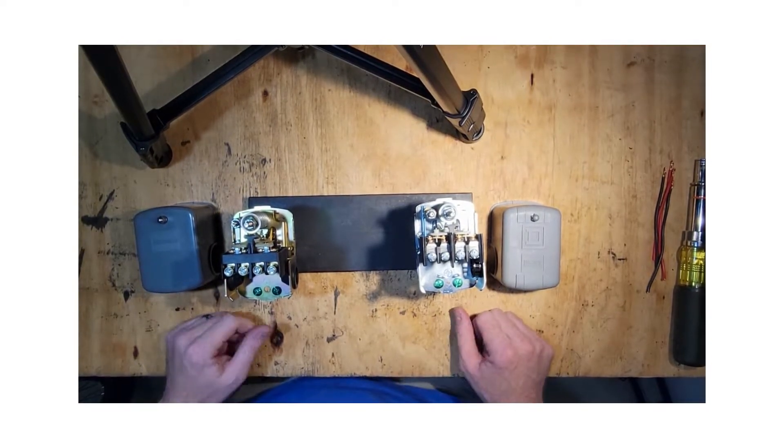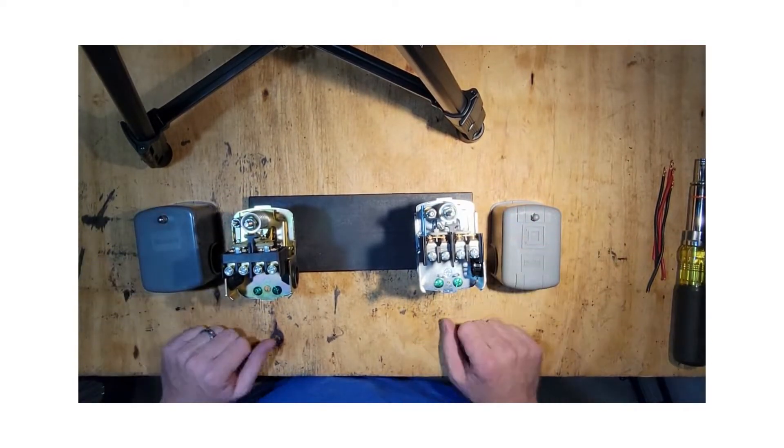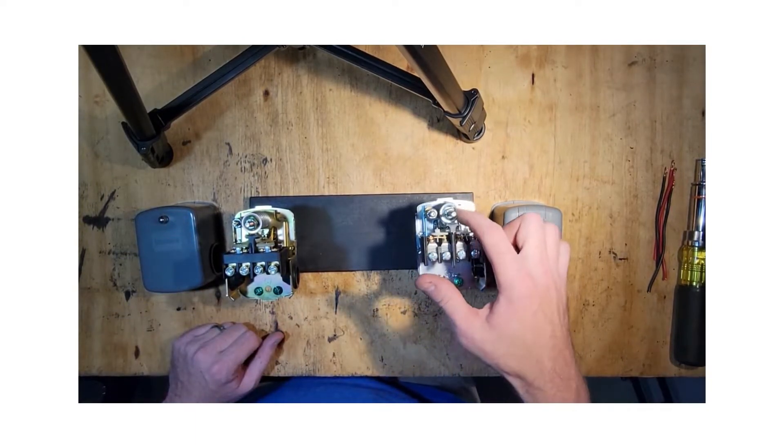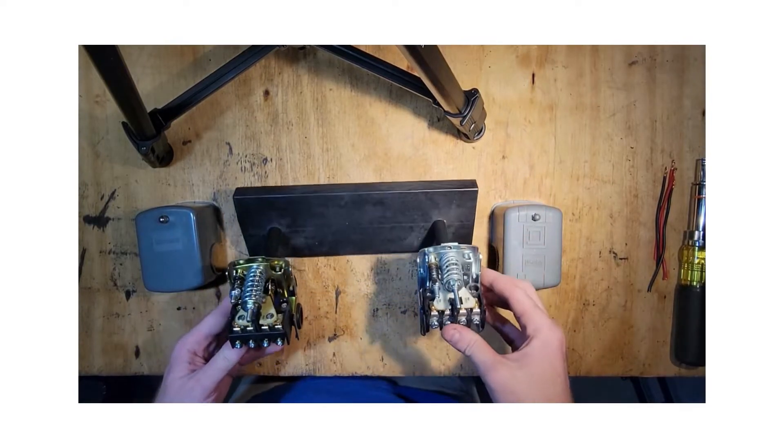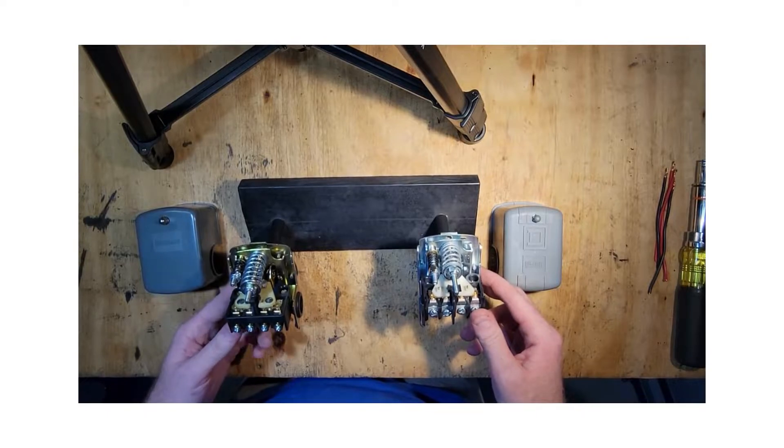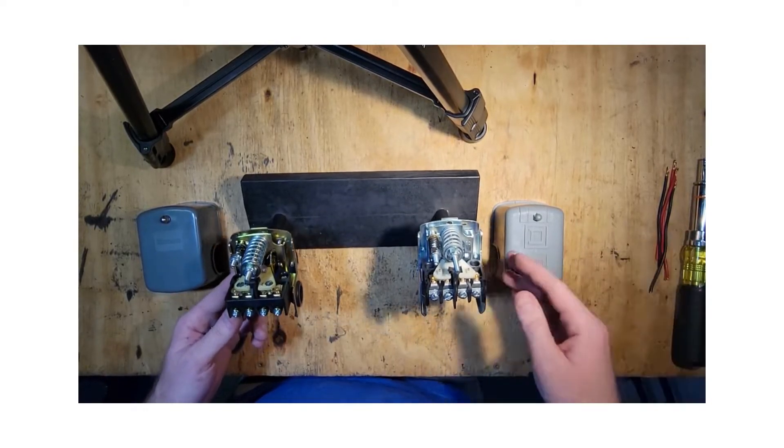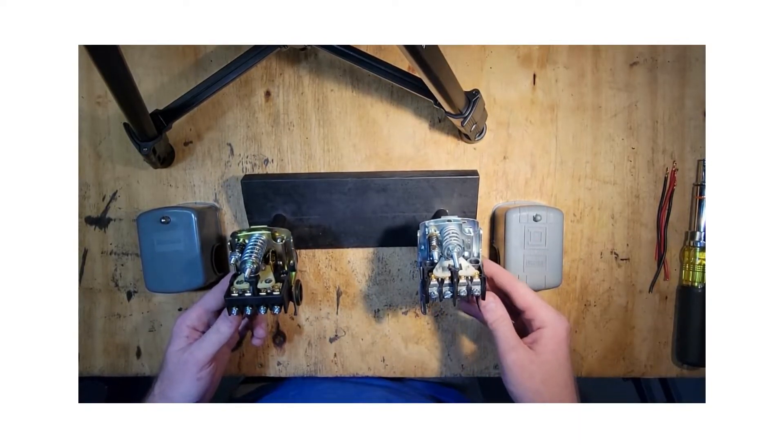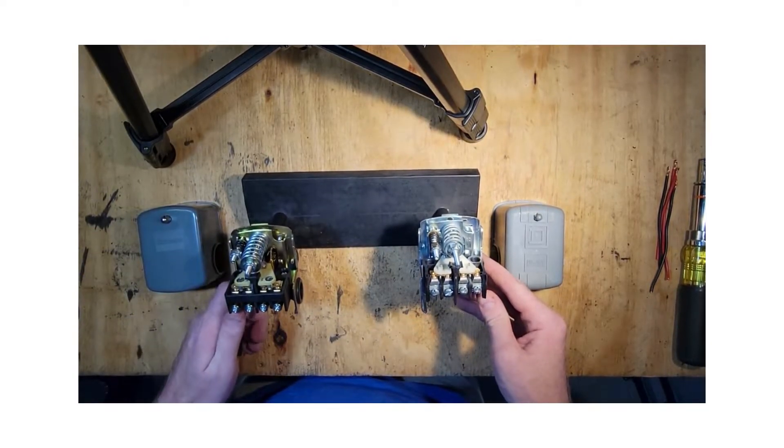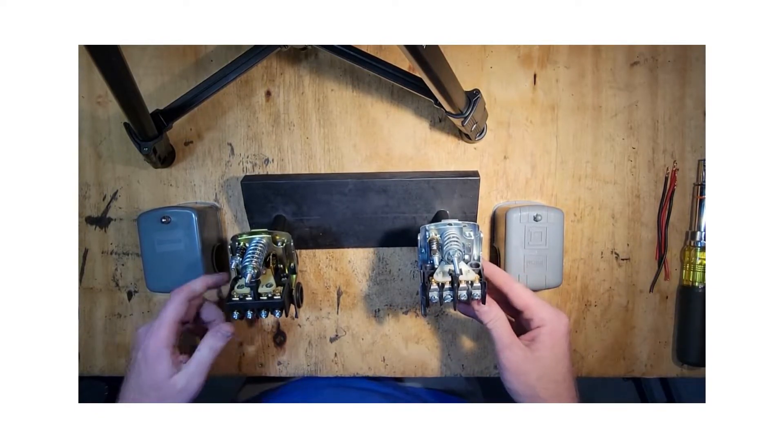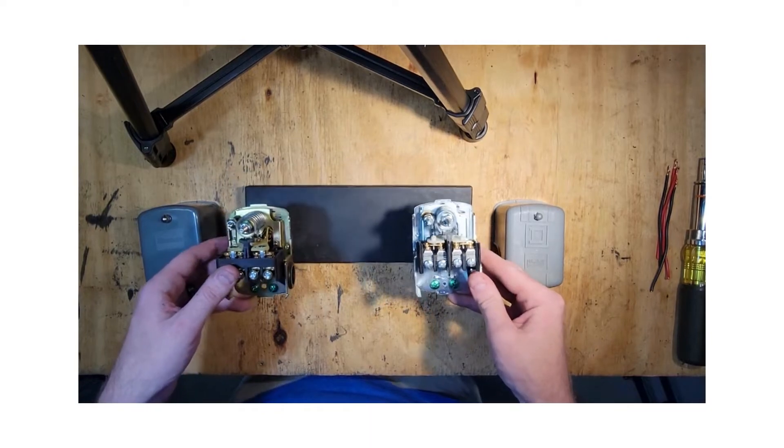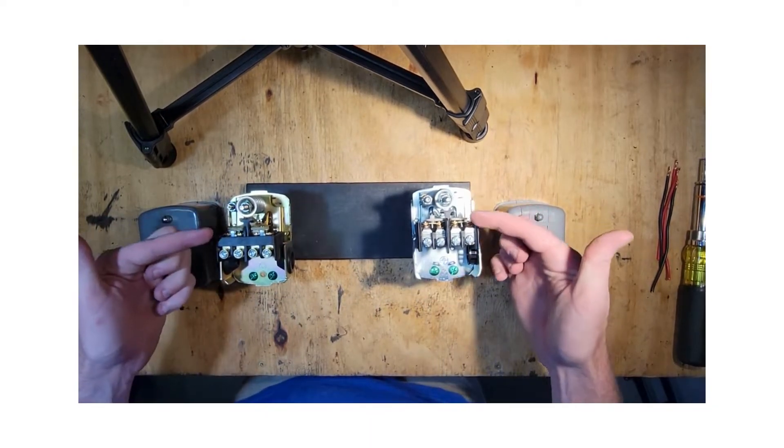They both have the same adjustment mechanisms. With the larger spring here, you adjust the on and off pressure equally—tightening it raises it, loosening it decreases it. The smaller spring, if you tighten it, increases the cut-off pressure only, and if you loosen it, decreases the cut-off pressure only.